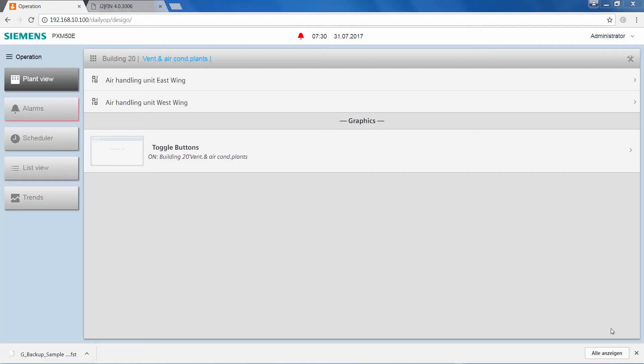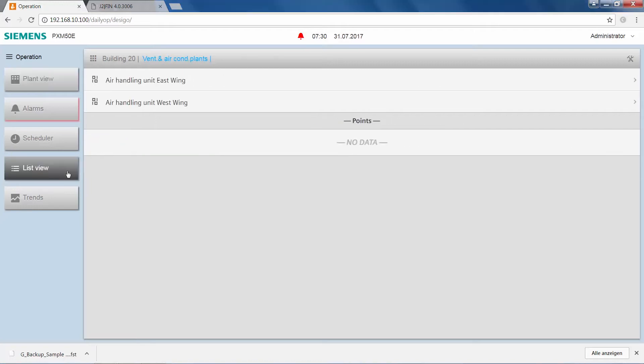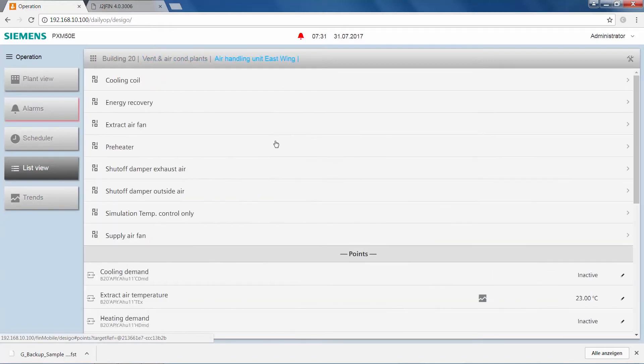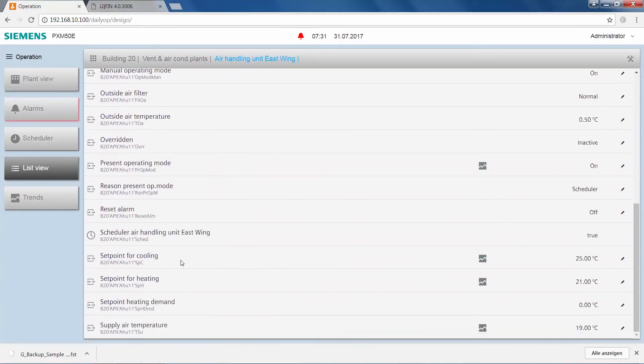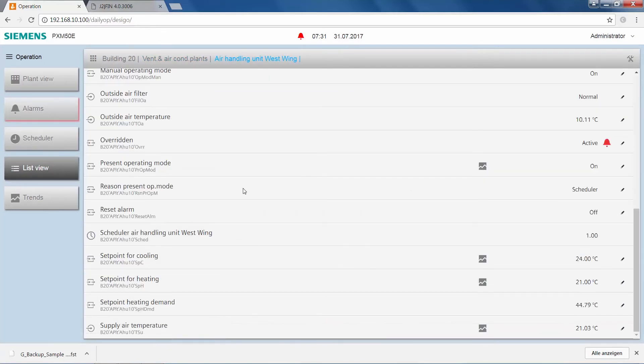The real challenge is of course not for the graphic to appear in the right place, but for it to connect to the right data points. Let's exemplify the point-to-graphics binding via the air handling unit's cooling set point. The current values of the cooling set points of the two air handling units can easily be inspected via the control points list view. Navigating there and drilling down into the east wing air handling unit, we see that its current cooling set point is at 25 degrees Celsius. Doing the same for the west wing air handling unit, we see that the set point is currently 24 degrees Celsius — so it's different.